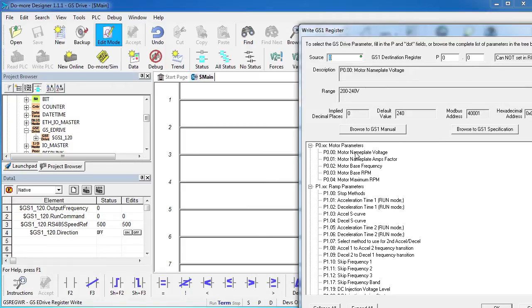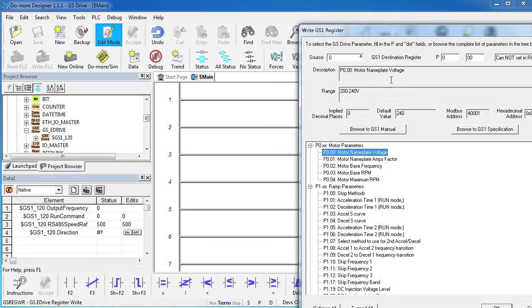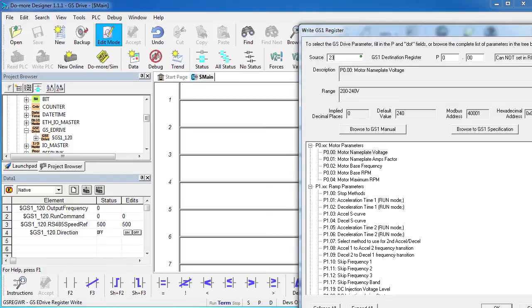The nameplate voltage. If I click on that, look what happens. It tells me the range of possible values for that parameter, a description of the parameter, a place to put my data, which I want that to be 230 volts, and what parameter that's going to go in – there are no implied decimal places – and the default value for this is 240. Awesome.